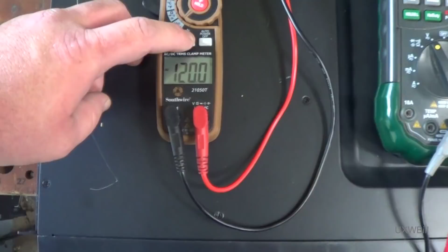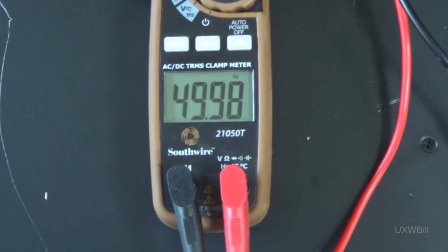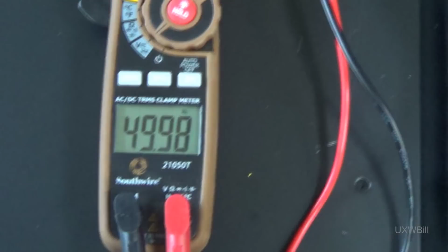Over here I have another meter hooked up. This one represents the variable. It's connected to an outlet on the back of this uninterruptible power supply. There's the voltage it's indicating, very precisely regulated, as you can see, by the dual conversion or online nature of this UPS. But more interestingly, if I choose the frequency measurement mode, you can see that it's operating at 50 Hertz alternating frequency.